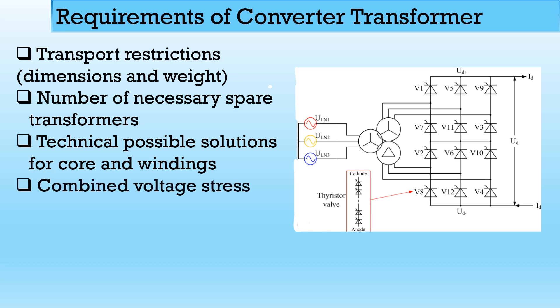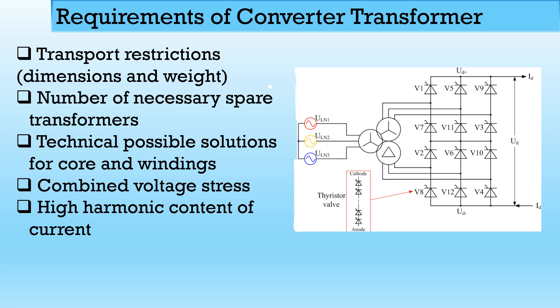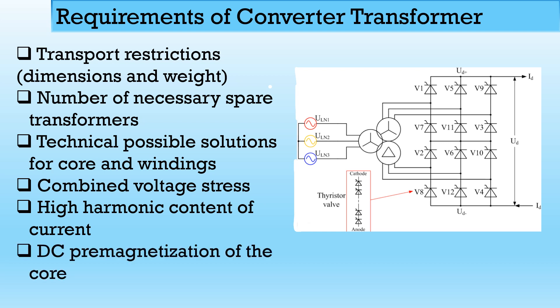There are combined voltage stresses — not only AC voltage stress but also stress due to DC voltage. The insulation of the transformer must withstand both AC and DC voltages. There is also high harmonic content of the current, since the power electronic converter at the secondary side introduces high harmonics into the system. Additionally, there is DC premagnetization of the core, because the primary carries a square wave type of current, which may cause DC premagnetization current in the core.